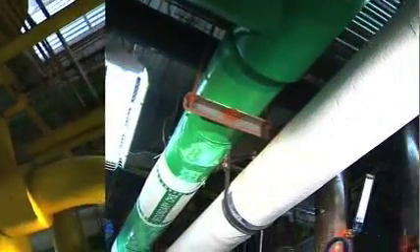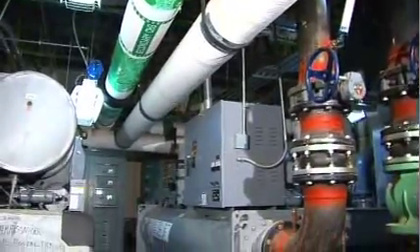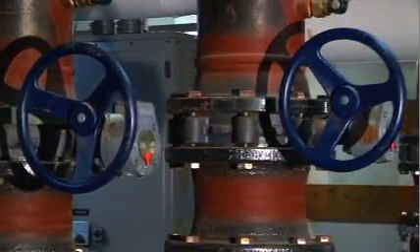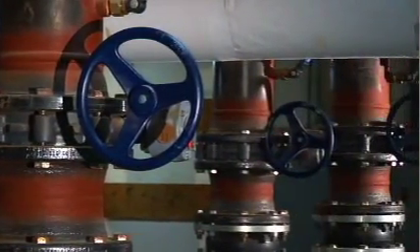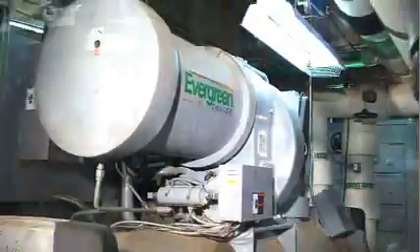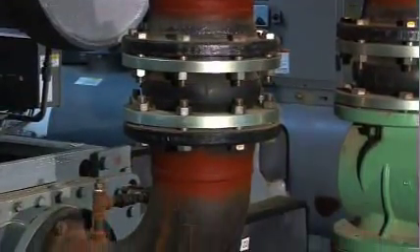Next door to the hot water heaters is the chilling room. These chillers are the air conditioning for the entire main learning center. The Track's HVAC team discovered that using the variable speed chiller unit in the winter saves energy costs and increases efficiency. During the summer, when the temperature is over 60 degrees Fahrenheit, the variable speed chiller is shut down and the high output chillers are brought online.